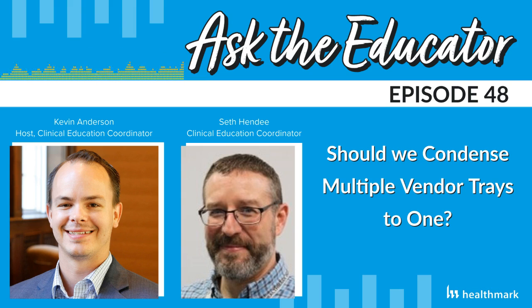But I've got to tell you, if I'm reading it with this thought in mind, and then the last one that I found: each family has been validated to a 10 to the -6 sterility assurance level. We love that, right? Now we just referred to the science, the thing that we need to think of. The manufacturer designed the proper placement of devices into each containment device layout. So now to get to 10 to the -6, they designed the tray in a specific layout to reach that. Once that layout is no longer there, is that 10 to the -6 validation accurate?